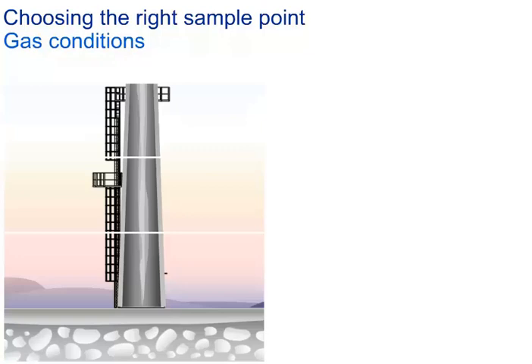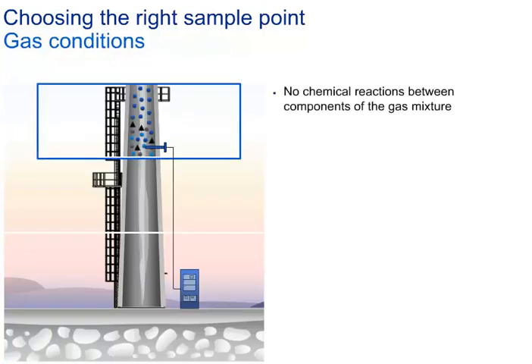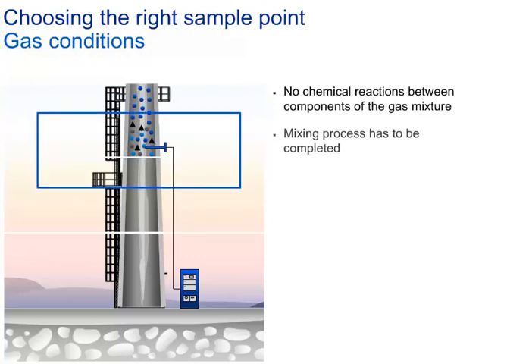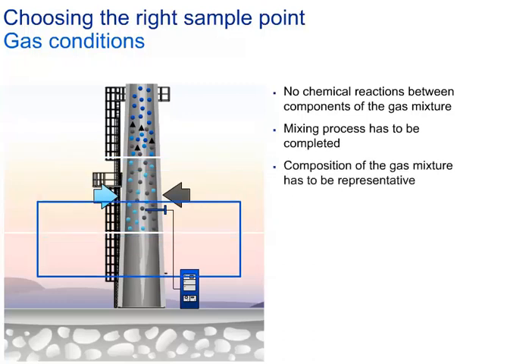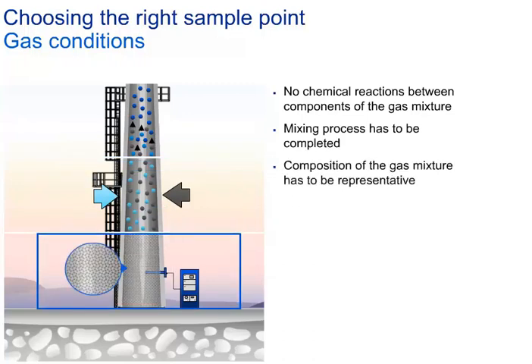Choosing the right sample point can also have a big influence on the measurement itself. It should be chosen according to the following criteria: chemical reactions inside the process should have ended so that there are no further reactions between components of the gas mixture; the mixing process must be completed at the sampling point so that the extracted gas contains the right mixture for a correct measurement; and in general, the composition of the gas mixture has to be representative for the information one expects from the sample point.